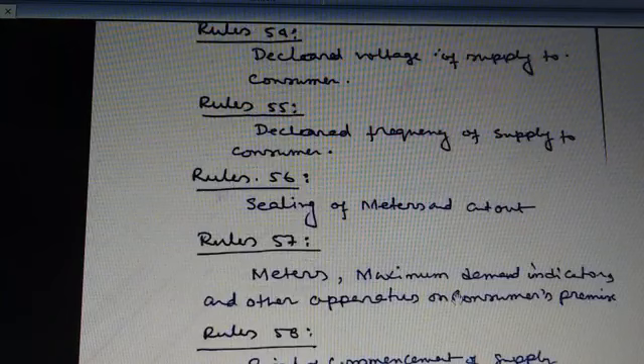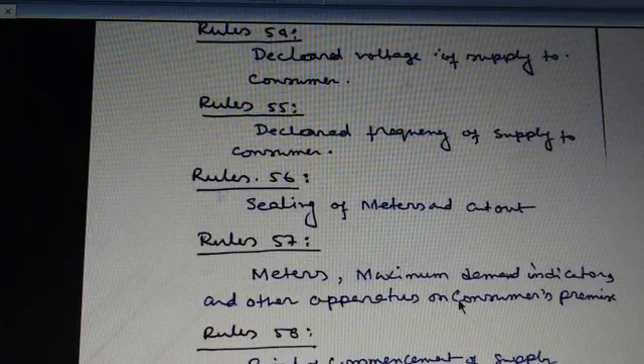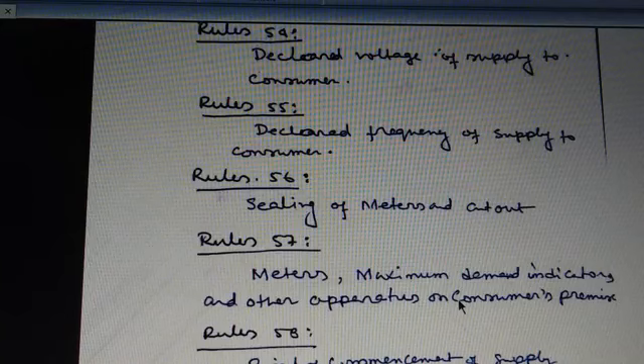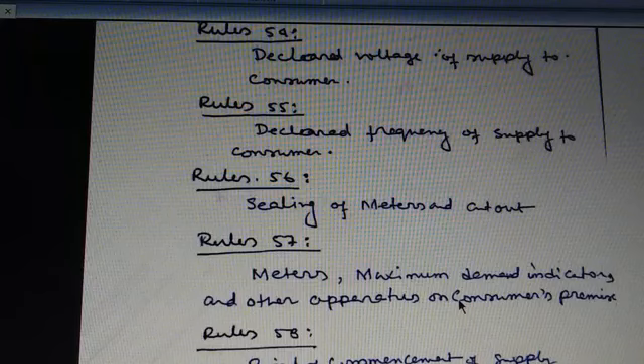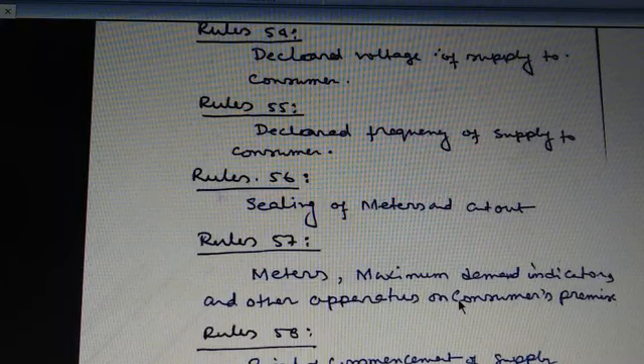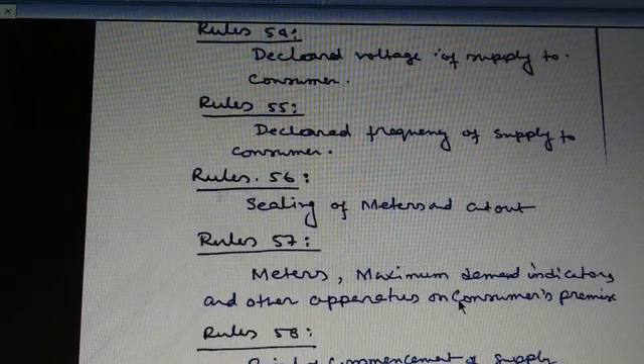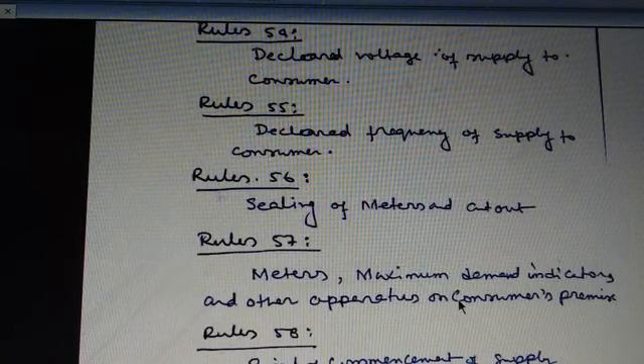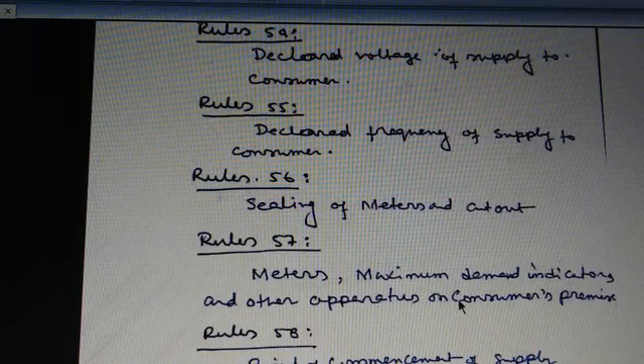Now rule number 57. Rule number 57 is related with the meter, maximum demand indicator and other apparatus on the consumer's premises. Any meter, maximum demand indicator or other apparatus placed upon the consumer's premises in accordance with section 26 shall be of appropriate capacity and shall be deemed to be correct if its limit of error does not cross 3% above or below absolute accuracy, when the load is between one-tenth of the full load and up to full load. Next, no meter shall register at no load, because all meters are registered with full load capacity, and before installation the meters must be calibrated against a standard meter.